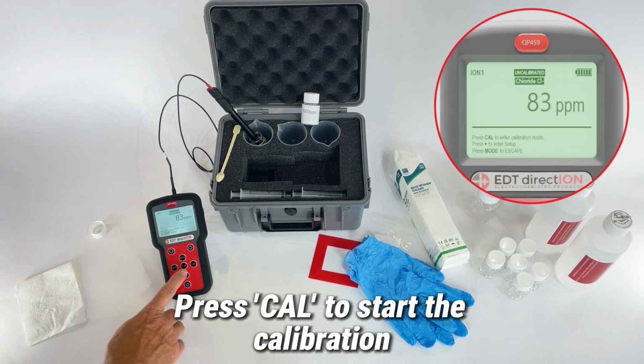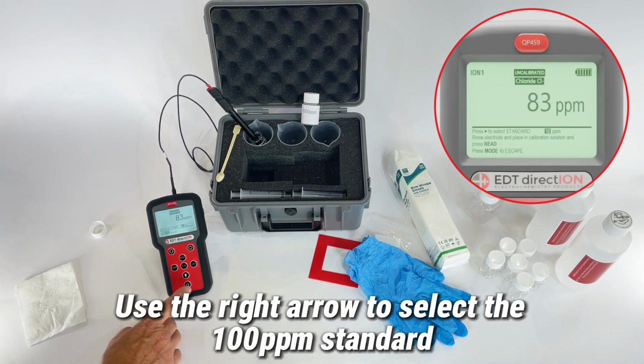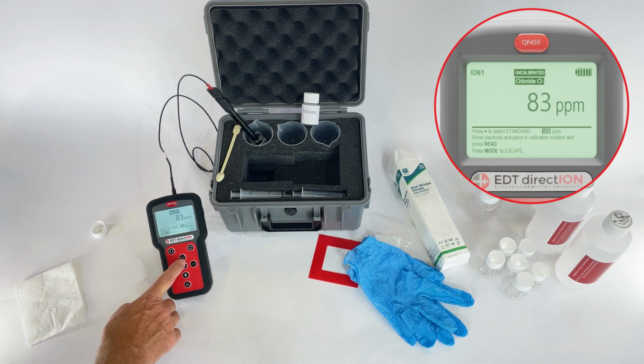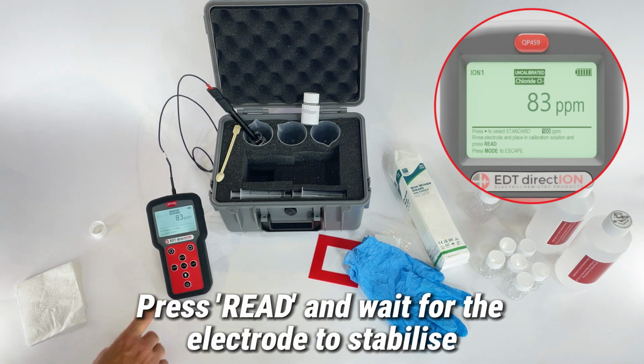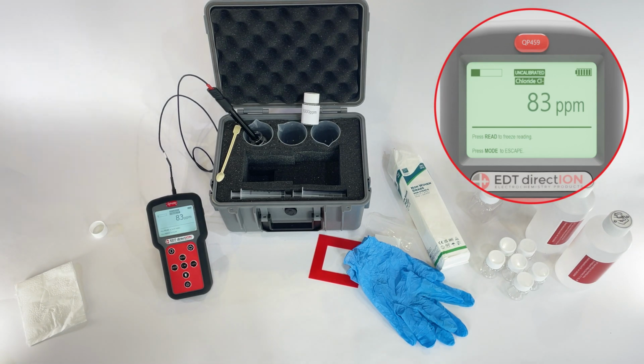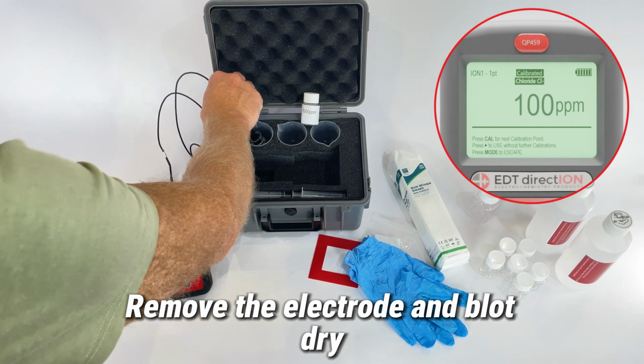Press Cal to start the calibration. Use the right arrow to select the 100 ppm standard. Press read and wait for the electrode to stabilize. Remove the electrode and blot dry.